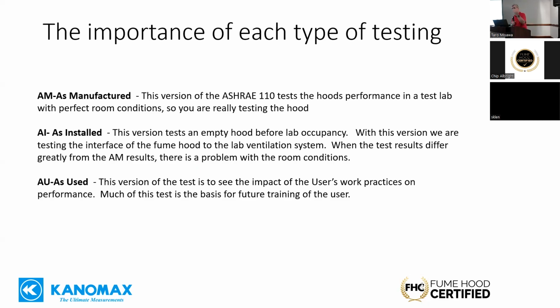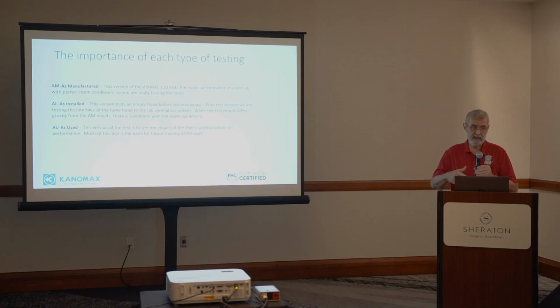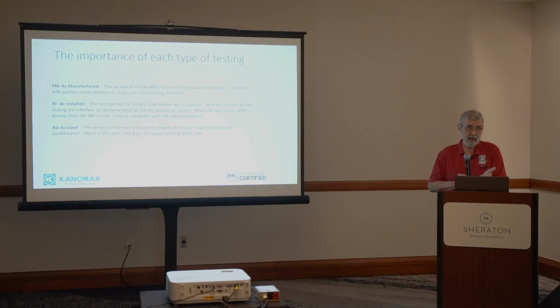Now we sell it and it goes out to the customer. That's as-installed—we'll probably have to change that term since AI is taking on a new meaning—but basically as-installed is testing an empty hood in the lab before it's been occupied, to see how it integrates with the laboratory ventilation system. If the results differ significantly from as-manufactured, you have a mechanical problem.